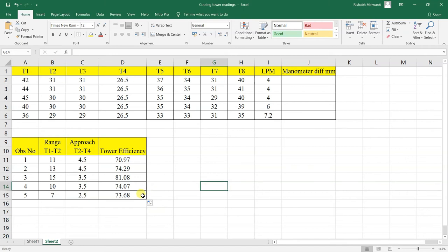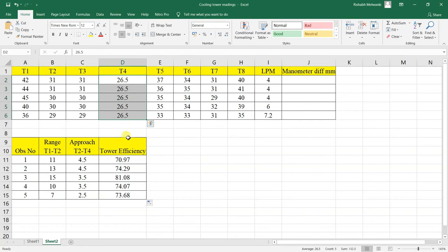The T4 reading shown here is not the actual value obtained during the experiment. This is because T4 is measured at the bottom of the cooling tower where the sensor is exposed to hot water, so there was error in that reading. Therefore, we used a sling psychrometer to read the wet bulb temperature, and that corrected wet bulb temperature value has been written here.